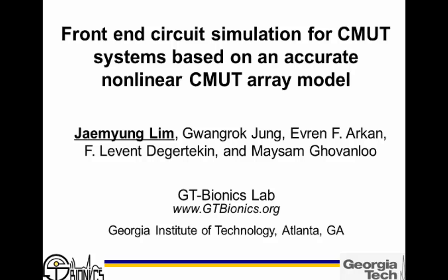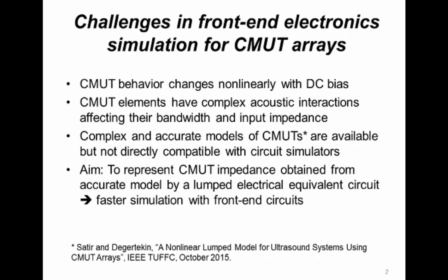I'm here to introduce our work, front-end circuit simulation for CMUT system based on an accurate nonlinear CMUT array model. Because CMUT behavior changes non-linearly with a DC bias, and also it has some complex acoustic interactions, we need to do the FEM simulation for the CMUTs. But it takes too much time and it requires too much memory. It's nearly impossible to use FEM simulation.